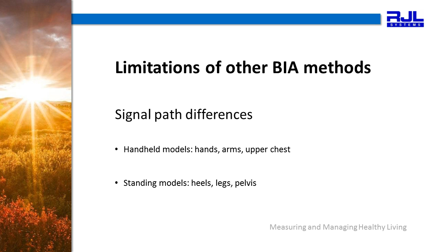There are also signal path differences. This is a good time to remind you that electrodes, electrode placement, devices, and software are not interchangeable, mix and match between companies. The protocol required for BIA is standardized by each device company.